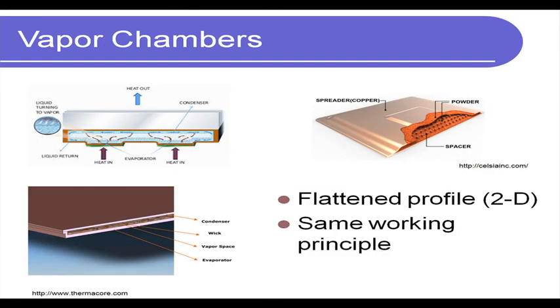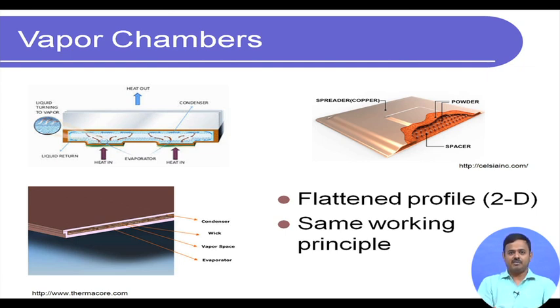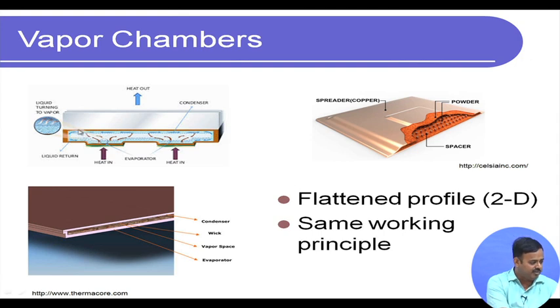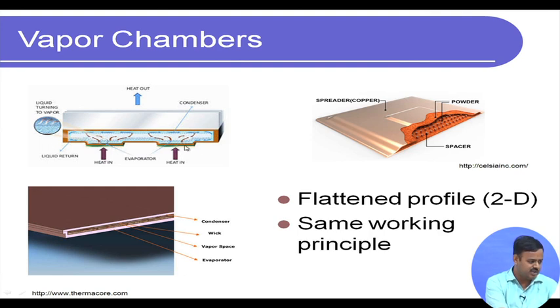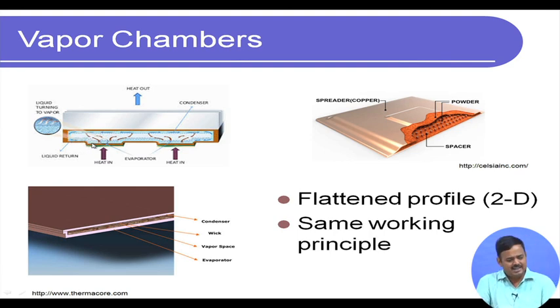Moving on to related devices: the vapor chamber works on the same principle as a heat pipe but is a two-dimensional structure. It acts as a heat spreader — a hollow two-dimensional casing with a wick along the internal wall. With multiple heat sources at the bottom and the entire top surface as the condenser, the liquid boils off, vapor rises to the condenser where it cools and returns via wicking action. It is essentially a planar, two-dimensional flat-profile heat pipe.